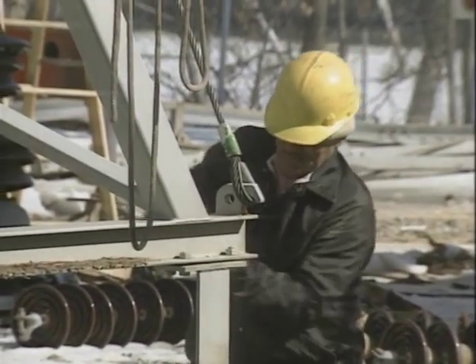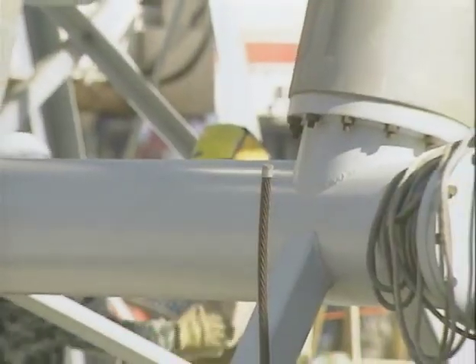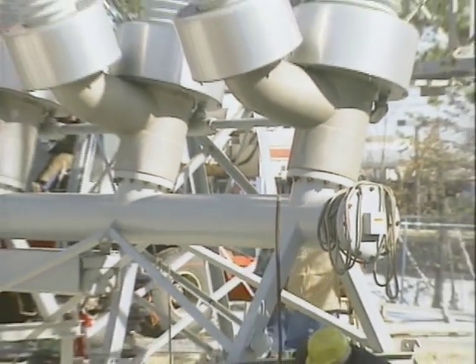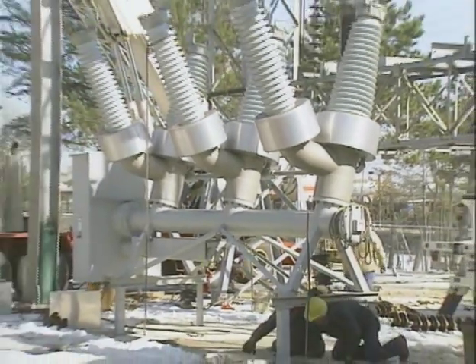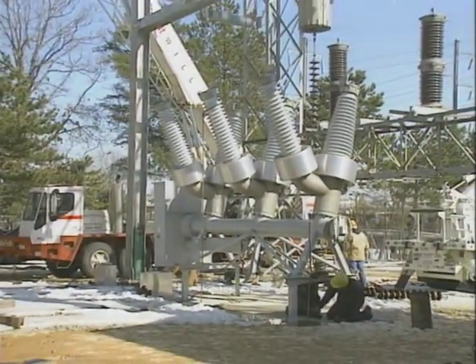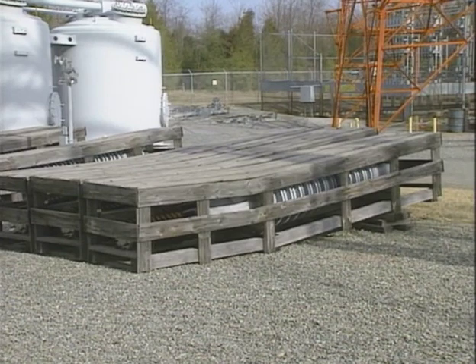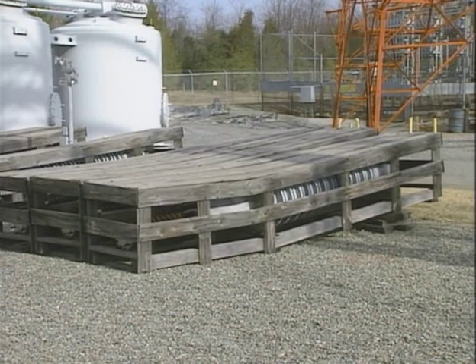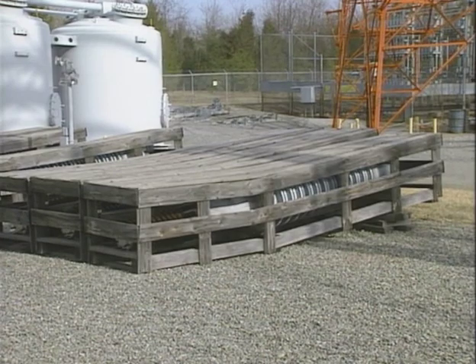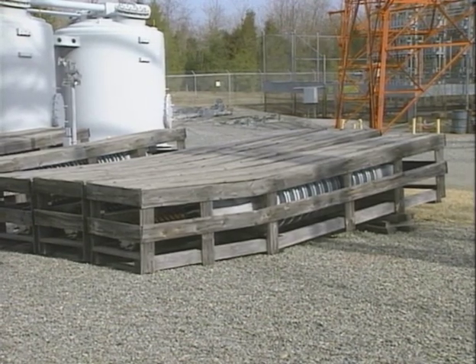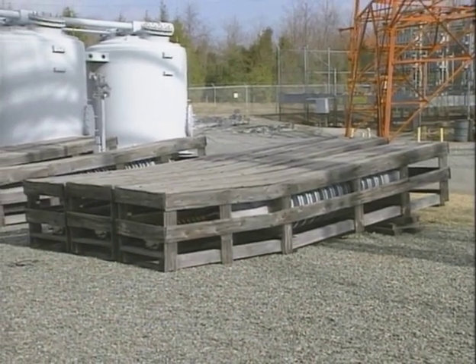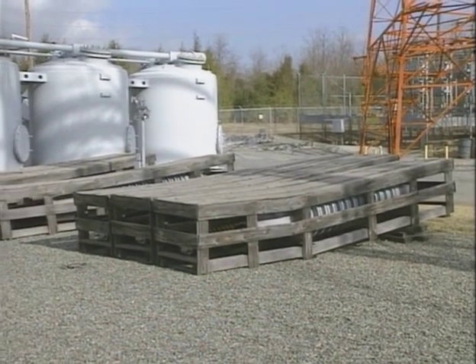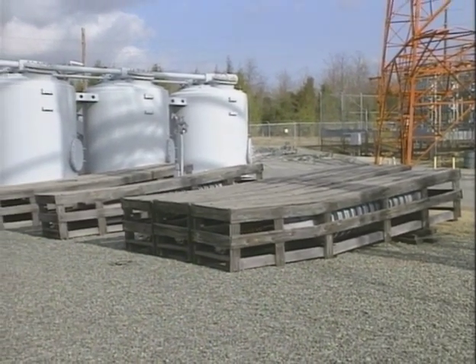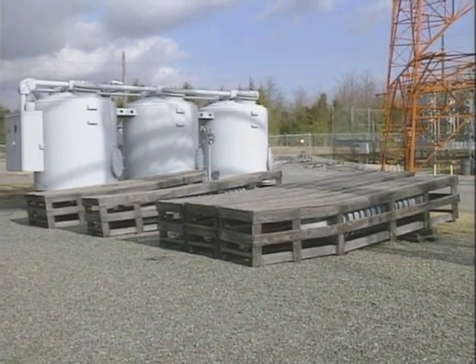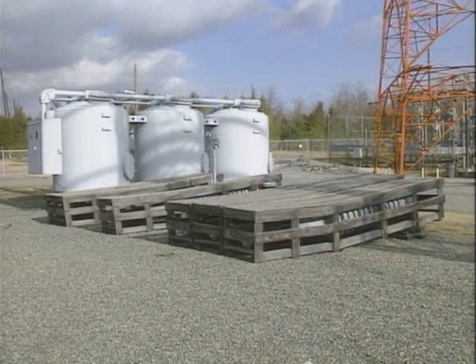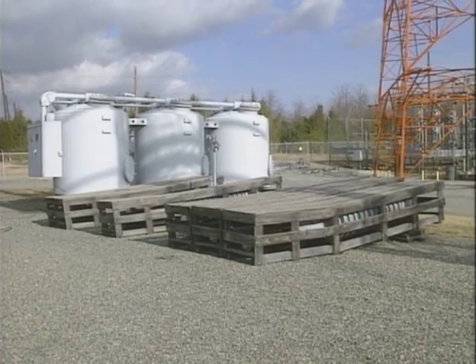Within a reasonable time after the breaker is secured, it should be connected to station ground, especially if the breaker is installed in an operating substation where it may pick up induced voltages. When a circuit breaker is delivered with its bushings packed separately, the bushings must also be hoisted into position using slings and a crane. The procedure for lifting and moving a bushing can vary with the size and type of bushing. For example, the bushings in these crates are large oil-filled bushings for the 230 kV breaker behind the crates. The bushings are very heavy.